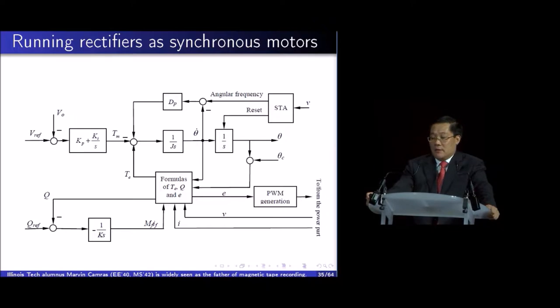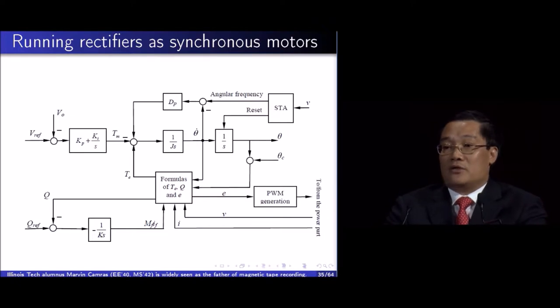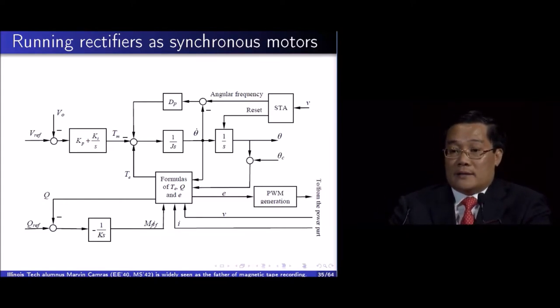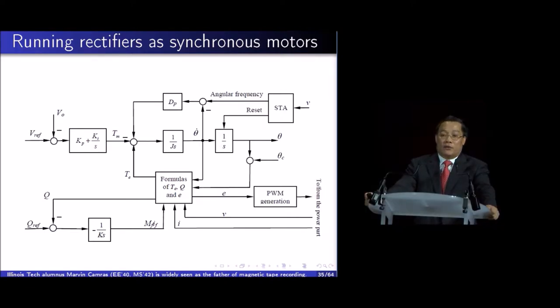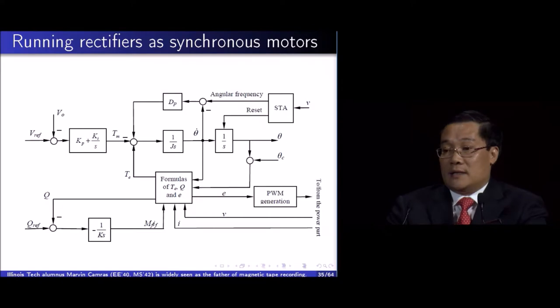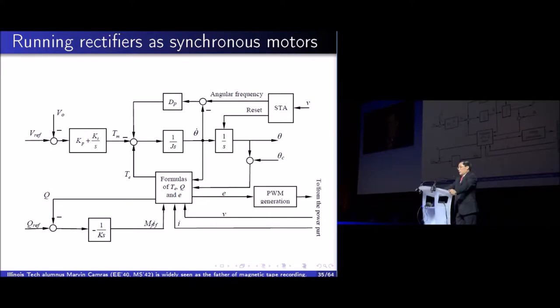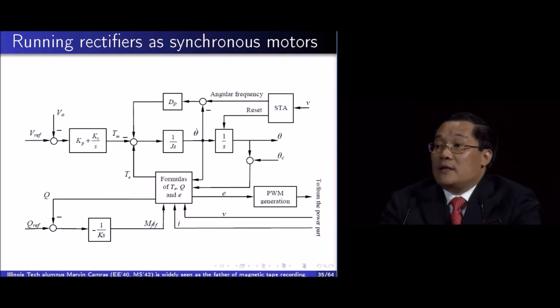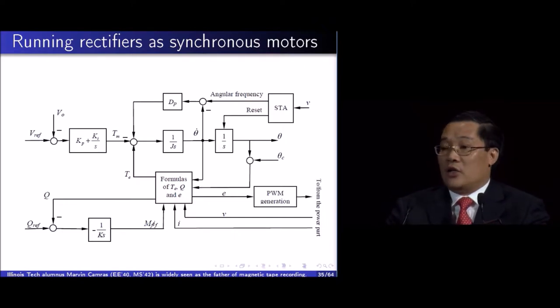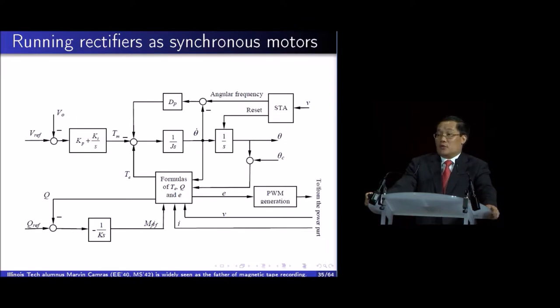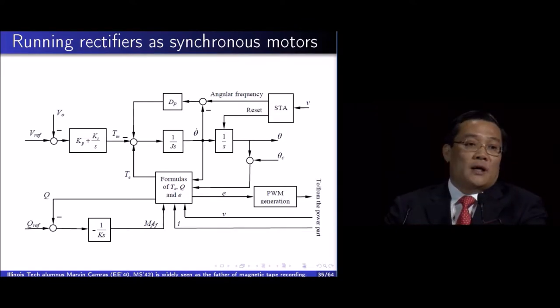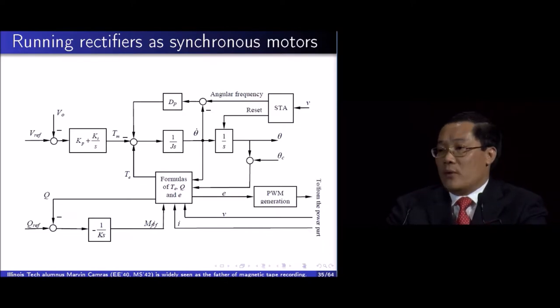We managed to operate rectifiers as virtual synchronous motors. What we did is similar to the synchroinverter concept: we adopted the mathematical model of a synchronous motor as the core of the controller for the rectifier. Then we added a small PI controller at the front end to regulate the DC bus voltage V0 to the reference voltage VREF. We can also add reactive power regulation to regulate reactive power Q through an integrator, changing the field excitation current, and if desired, add voltage control to the controller as well.